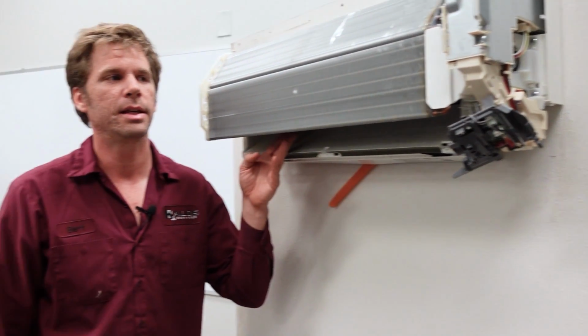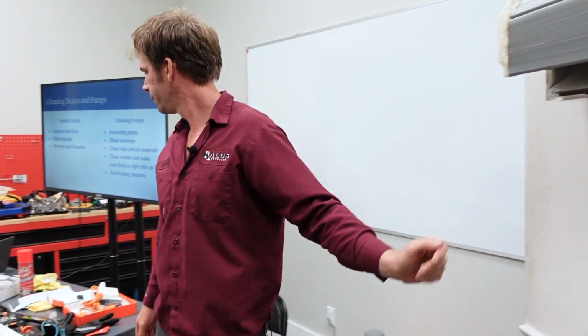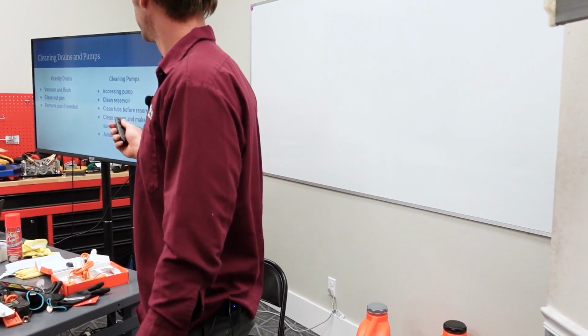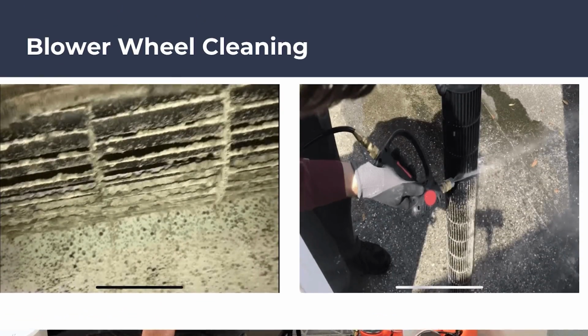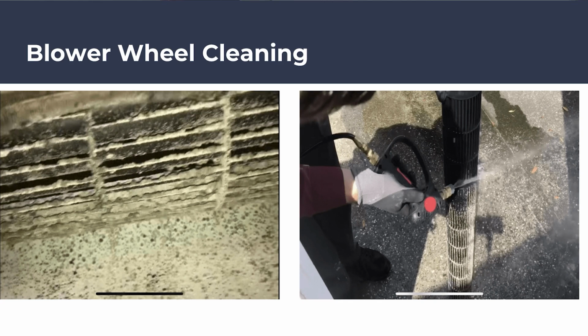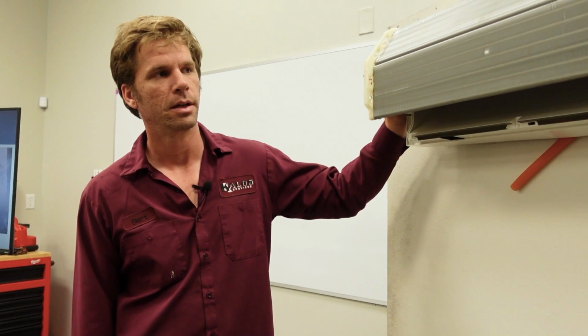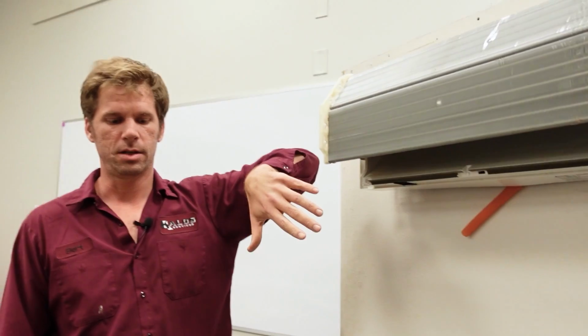Okay, so the next thing we're going to talk about is blower wheel cleaning. Now that we've gone over cleaning our drains and our pumps - the blower wheels can get pretty nasty, and you guys have all experienced that. Dust builds up on there, and then airflow starts becoming an issue. You can get freezing, you will sometimes be pulling freeze codes. But often the customer is going to have stuff spit into their space, like little black bits, and it'll smell weird. You just don't have the airflow to push across the whole space and cool the whole room.